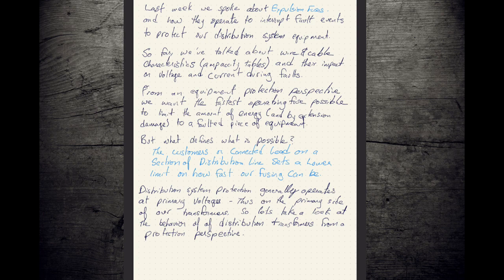So, we do have customers attached to our system, and they are going to be drawing current, which means we're going to have energy flows. Some of those customers are going to be industrials who have great big motors that they're going to be starting, not always in the gentlest fashion, and we're going to see these temporary overloads that will appear on our system and then disappear. And so we have to be able to adjust our protection, our fusing, to make sure that it's sensitive enough that it can detect a fault, but not so sensitive that it's going to operate during these very normal, routine, run-of-the-mill sort of events.